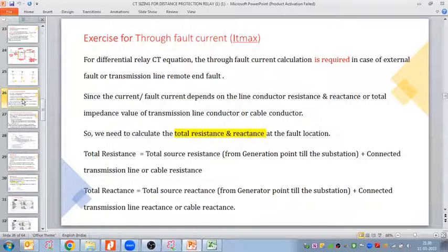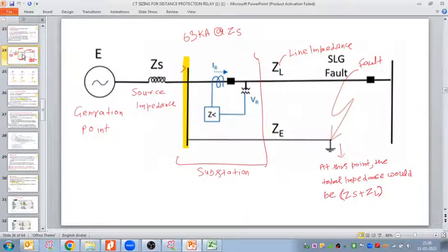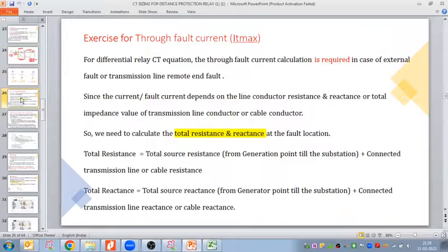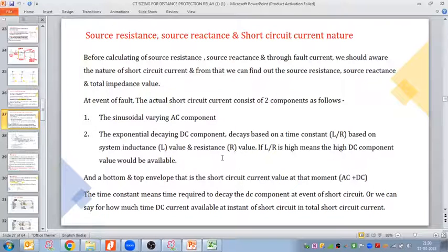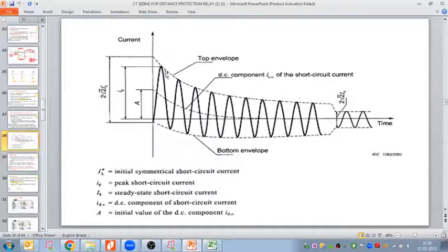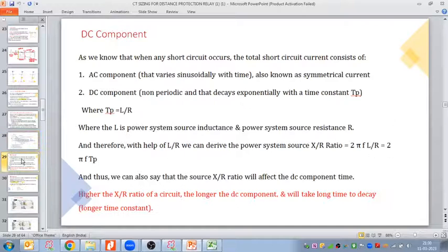Now coming to the through fault current calculation. It would be my source resistance plus my transmission line resistance. After that we can calculate the through fault current here, right? Before coming to the through fault current, or the short circuit current at the remote point, we need to understand the nature of the short circuit current. When any fault happens, the short circuit current has two components: one is the sinusoidal AC component, plus an exponentially decaying DC component, right?